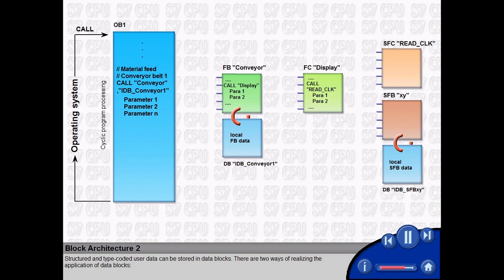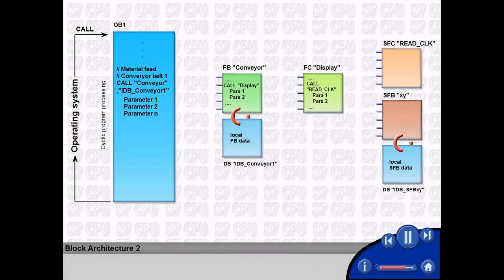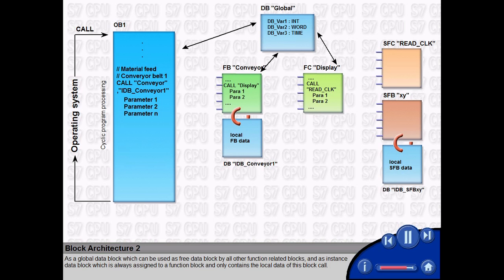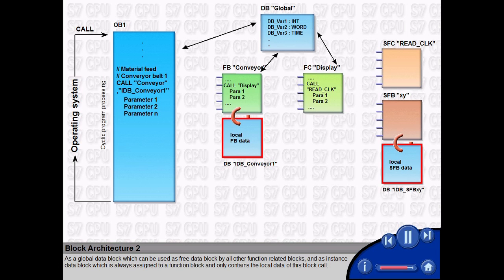Structured and type-coded user data can be stored in data blocks. There are two ways of realizing the application of data blocks. As a global data block, which can be used as free data block by all other function related blocks. And as instance data block, which is always assigned to a function block and only contains the local data of this block call.